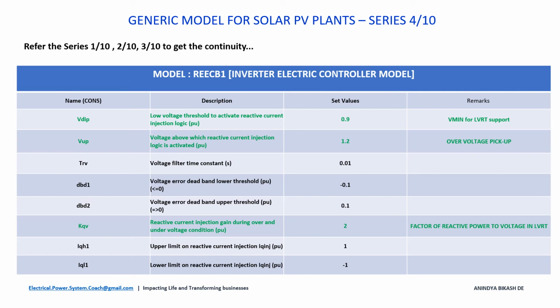So other parameters, that upper limit on reactive current injection and lower limit on reactive current injection. Usually this is the inverter rated current limit 1 per unit, or you can put it 1.1 per unit as well as minus 1.1 per unit depending on the inverter. So these are also default parameters.